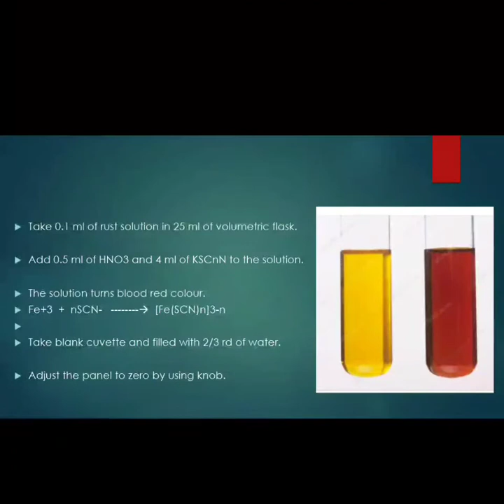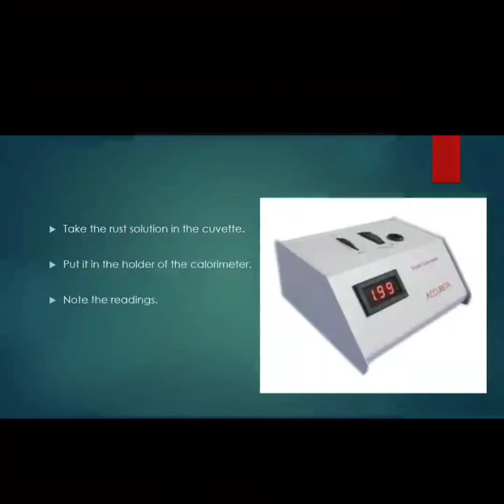A clean blank cuvette is taken and filled with distilled water to 2/3 of the cuvette. Clean the outside of the cuvette with the help of tissue and insert it smoothly into the cuvette holder of the colorimeter. The reading on the panel is adjusted to 0 by the knob, and remove the cuvette. After adjusting the panel to 0, take rust solution in the cuvette, clean the outside of the cuvette with tissue and insert it smoothly into the cuvette holder of the colorimeter. Note the readings.